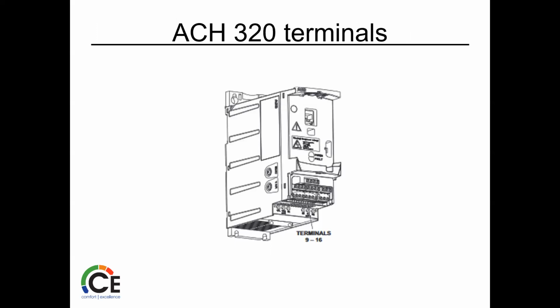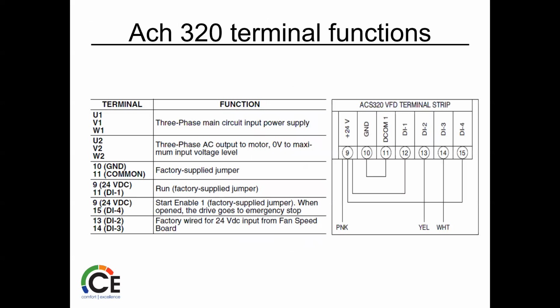So again, terminals 9 through 16 there, some low voltage inputs, just like the other one. Same thing: power in, power out, ground, common, factory supplied jumper. The terminal itself is powered 24 volts. Start enable, we need that powered all the time, so that stays there. And then factory wire for 24 volt VDC input from the fan speed board. So that's 13 and 14 is DC.